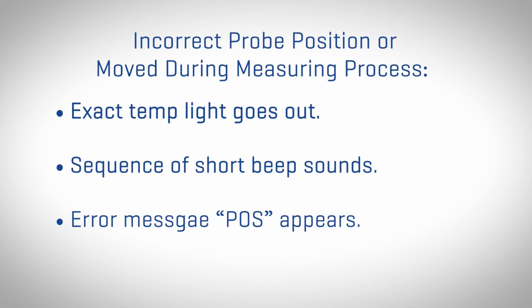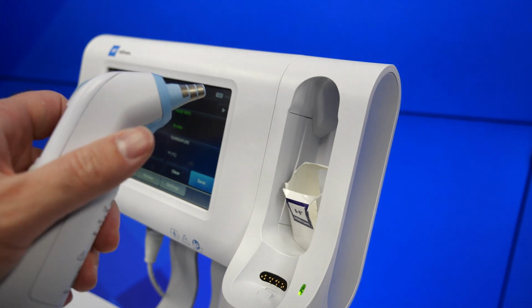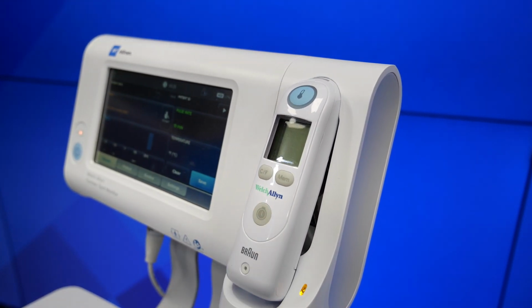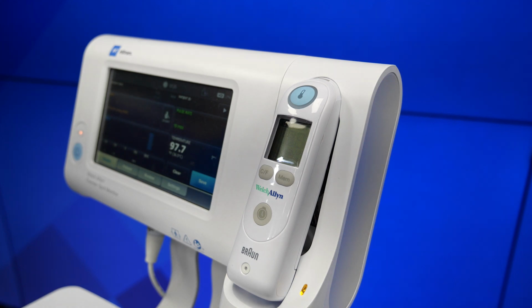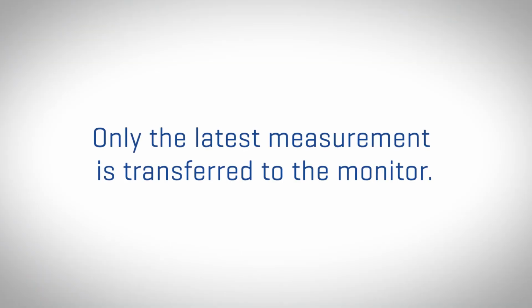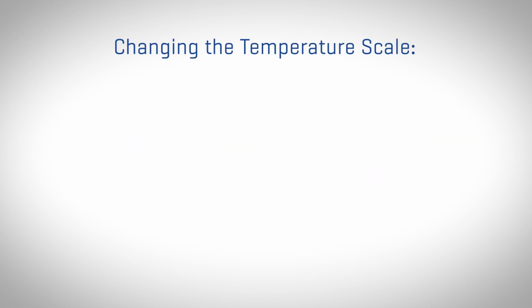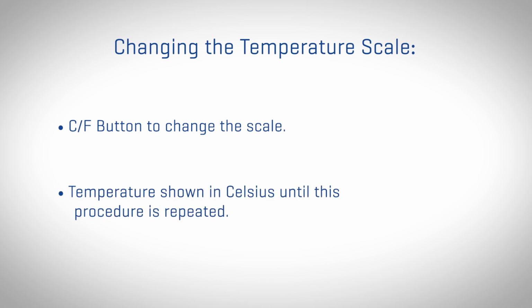When you are finished taking the temperature measurement, press the ejector button to eject the used probe cover. Return the thermometer to the dock and the LED will flash while the measurement is being transferred. After the transfer is complete, the temperature and the temperature scale appear on the device screen. Keep in mind, only the latest measurement is transferred to the monitor. If you'd like to change the temperature scale on the ear thermometer, press the C/F button to change the scale. When turned on again, the temperatures will be shown in Celsius until this procedure is repeated.